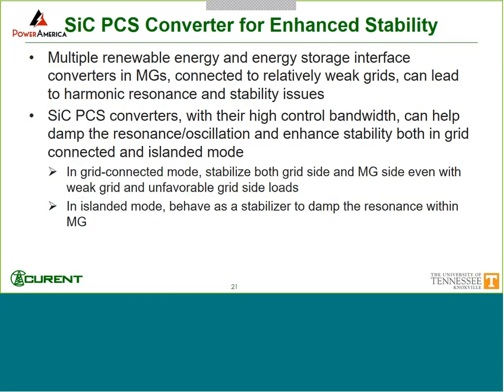For stability, we look at it in two ways, and one is to connect to the grid. As we know, when you connect your converter to a very strong grid, probably there would be no issue. But in some cases, you don't always have a very strong grid, and sometimes you may have loads that exhibit unfavorable conditions. With that, there could be small signal stability issues like harmonic resonance. That could happen in both islanded mode and grid connected mode. When that occurs, what you can do is use control to help reformulate the equivalent impedance. But the condition for that is you would have to have enough bandwidth to do so.